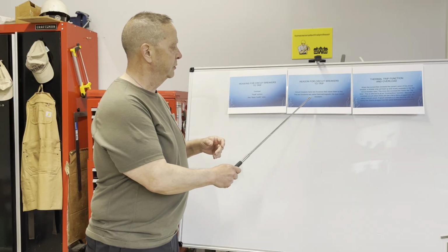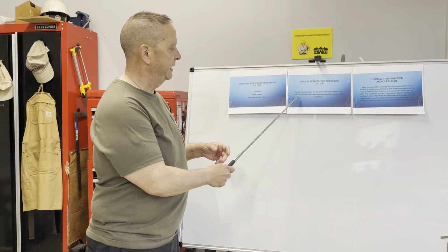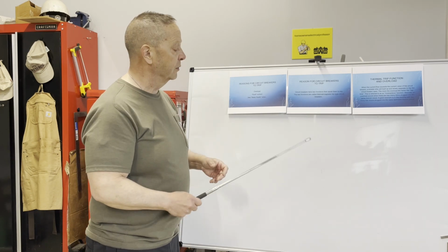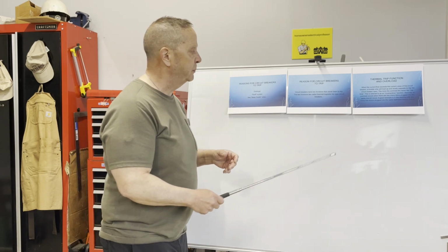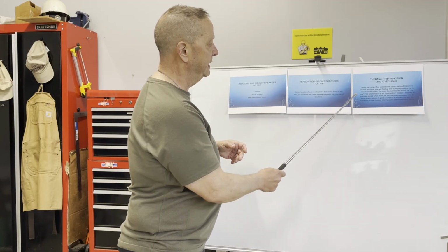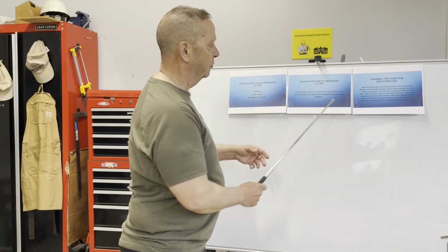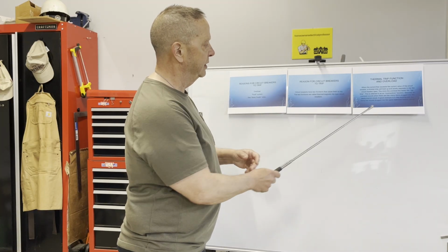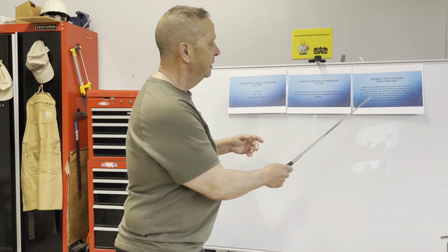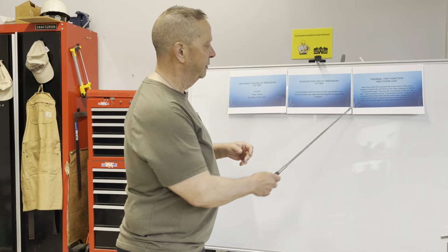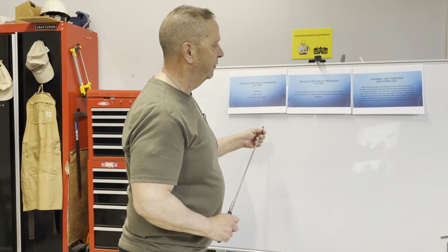Now, circuit breakers have two functions. Like I said, one function is called the thermal part, which is what allows an overload to trip it. So I'll just briefly go over it again. When the current flow exceeds the current value of the circuit breaker, there's a bimetal strip. It heats up, slowly separates, and trips the circuit breaker open. The more the overload, the faster the trip time. This is referred to as an inverse time function.